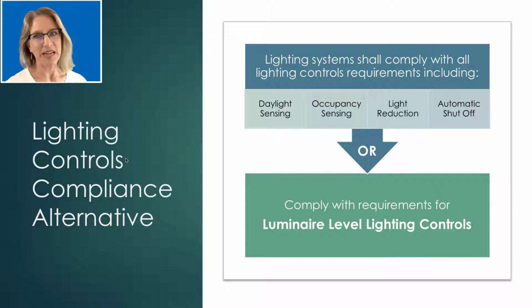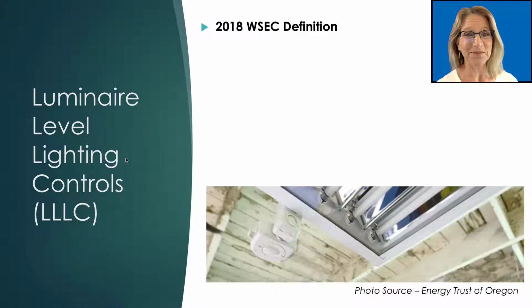Within the scoping statement of the automatic lighting control section of the code, there is an alternative compliance path defined for spaces served by Luminaire level lighting controls. So the project can either comply with all applicable daylight sensing, occupancy sensing, light reduction, and automatic shutoff control requirements, or it can comply with the requirements for Luminaire level lighting controls.